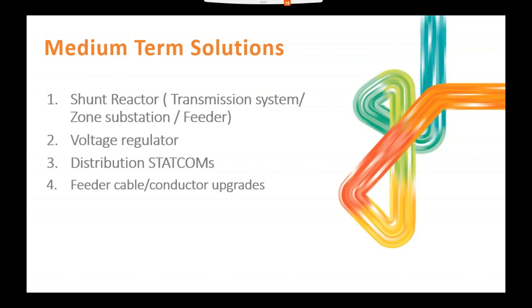We're changing standards in our power transformers so they have just as many, or even more, tap-down positions as tap-up. Historically it was very rare to require tapping the voltage up; transformers needed to tap up because of load drop on the network. But recently we've found you also need to pull that voltage down because of reverse power flows from solar. So our historical standards versus what's needed now is non-symmetrical, because no one thought of this issue years ago.